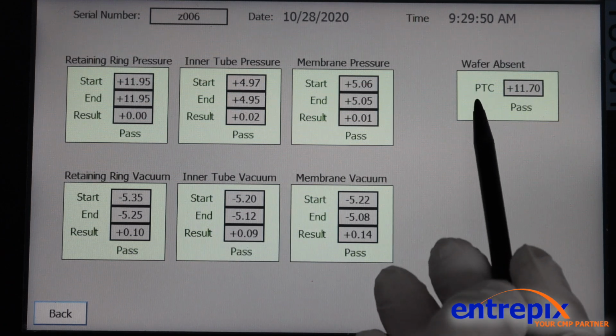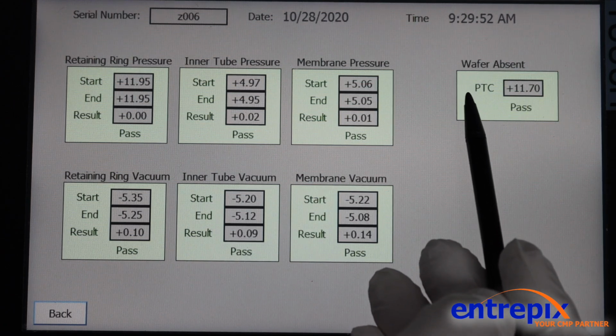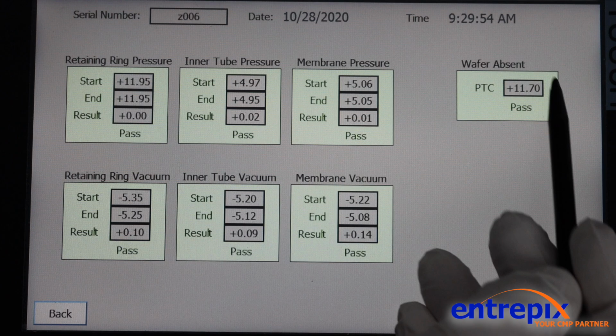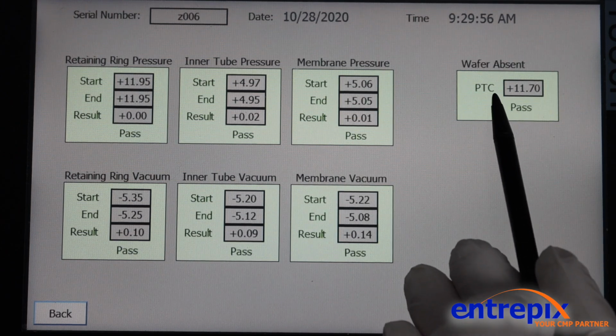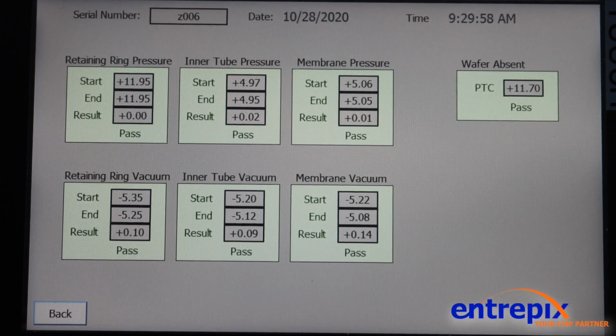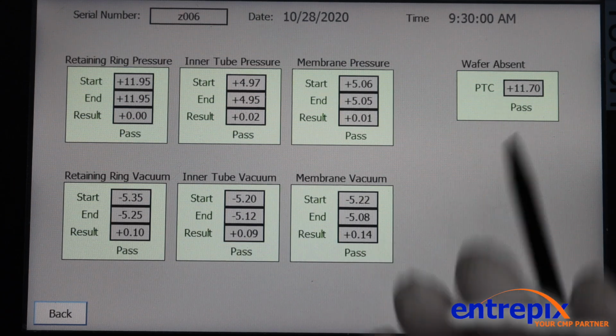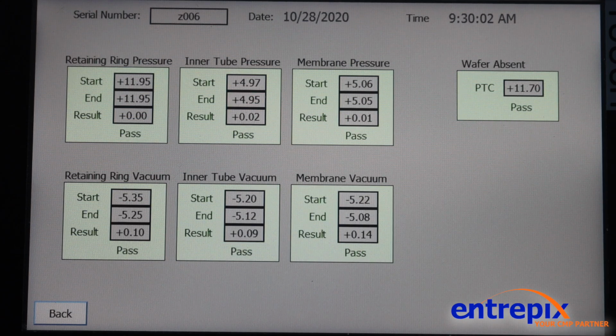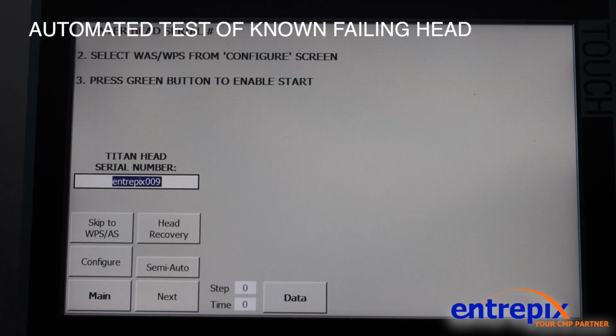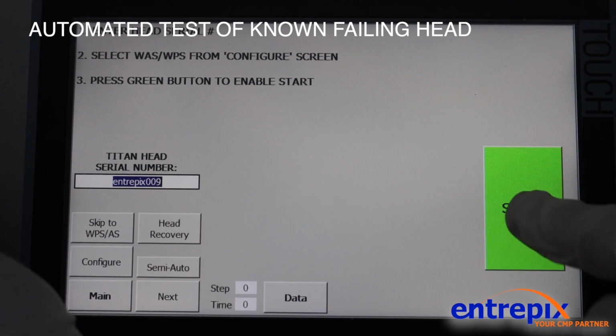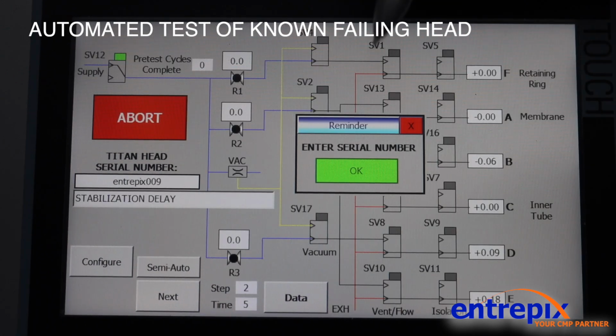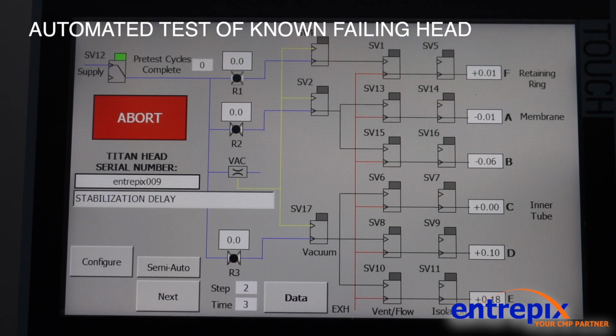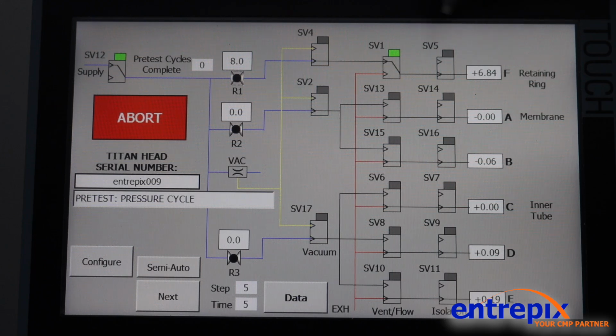The final indicator is the wafer present test result. And this is indicating that the inner tube held a positive pressure during the duration of the test, indicating a passing wafer present sensor. And then simply hit the manual start button and the software start button using both hands. We've already entered the serial number, so we'll just click OK there. And then you'll see it here. It'll exercise through all the automated functions that we had highlighted on the previous video.